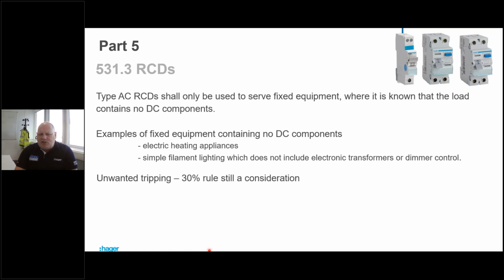Now, unwanted tripping. Okay, this was discussed in the 18th. What we basically said was we want to ensure that we do not preload a split load board with 2 RCDs by more than 30% of standing earth leakage. We're trying to rule out nuisance tripping. It's still a consideration. It's still something we must think about.